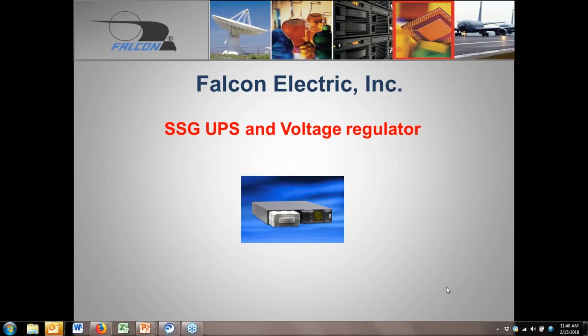But as I mentioned before, based on the charging, based on the voltage level we charge to, and the safety features of the charging itself, we are well under the requirement for that battery. Therefore, we don't require a different type of charger, because our chargers inherently have a cutoff voltage that is within the battery cutoff level. So even if the battery charger either floats away or goes under or fails, the charger will be cut off, and the UPS will trigger its summary alarm when that happens. That is all part of the safety feature of the integration of the pack and the battery itself, and in addition to the balancing circuit inside the battery, there's also fuse protection against short circuiting and overcurrent. So all in all, the simple answer is no. There is no difference in charging between the lead acid and the lithium iron phosphate. Okay, thank you.